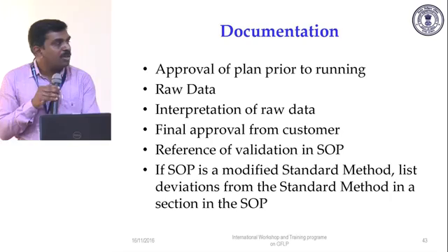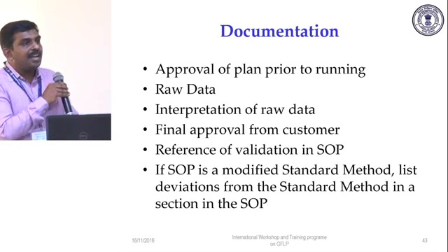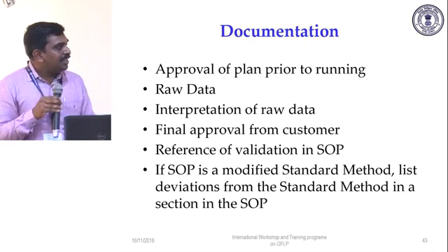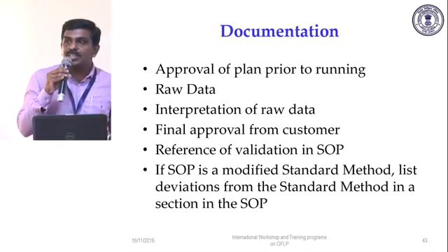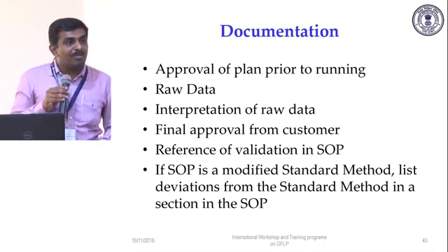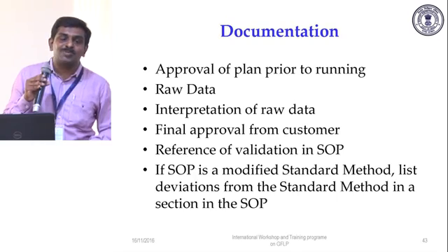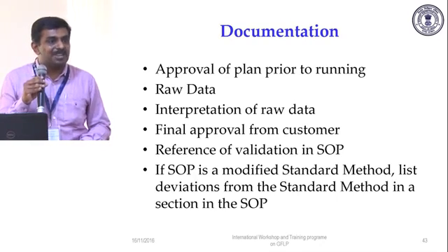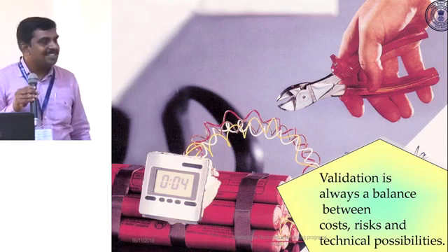Again, just to show you what documentation is, just a generic slide, what should be there. You should have a validation plan, and the outcome will be a validation report. This I have taken from ISO IEC 17025, but people don't read this. It is in Note 3, I think, of ISO, because notes we don't read. But I think ISO IEC 17025's notes are very, very important. And in one of the notes it is written, validation is always a balance between cost, risk and technical possibilities. Yes, you have to make your own judgment.